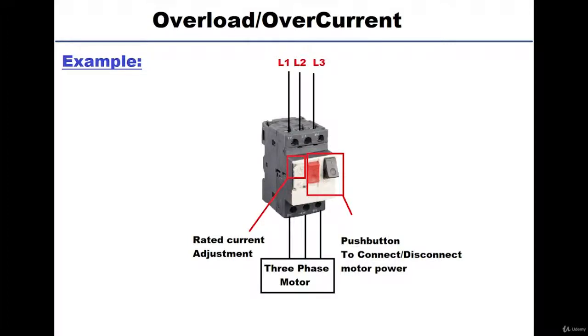You connect the three phases to the input, you take the three phases from the output, and you directly connect it to the three-phase motor. It's like a circuit breaker, but this one is designed just for motors. You have a knob on the left which is used to adjust the rated current. They have an advantage over circuit breakers in that their response is a little bit faster.